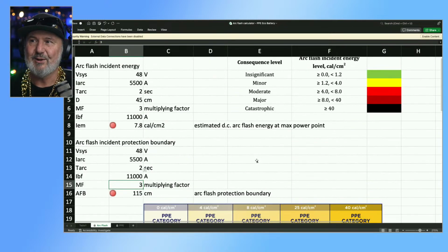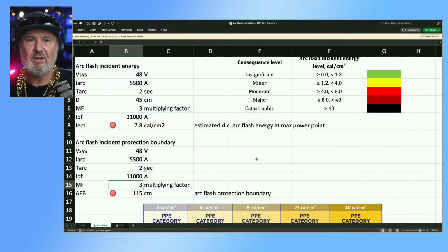But I do have good news for you. The good news is it's very easy to massively reduce, using exactly the same battery, the arc flash incident energy and boundary with a $20 product. It's called a fuse. So if you put a fuse within the string, so let's say you've got a 48 volt battery system, it's lead acid, it's made of 24 2-volt cells. It's been so long since I've done a lead acid battery, I've forgotten that.